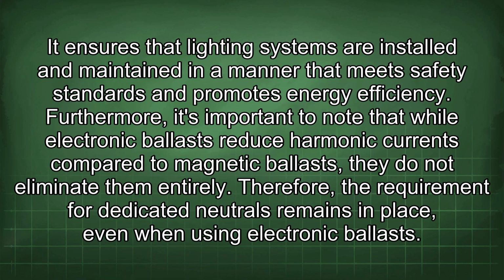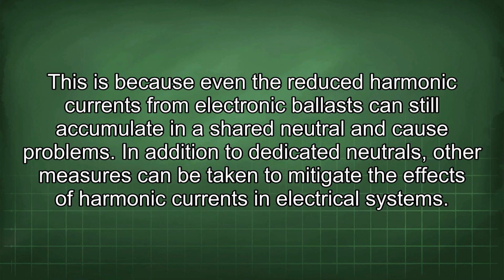It ensures that lighting systems are installed and maintained in a manner that meets safety standards and promotes energy efficiency. Furthermore, it's important to note that while electronic ballasts reduce harmonic currents compared to magnetic ballasts, they do not eliminate them entirely. Therefore, the requirement for dedicated neutrals remains in place, even when using electronic ballasts.